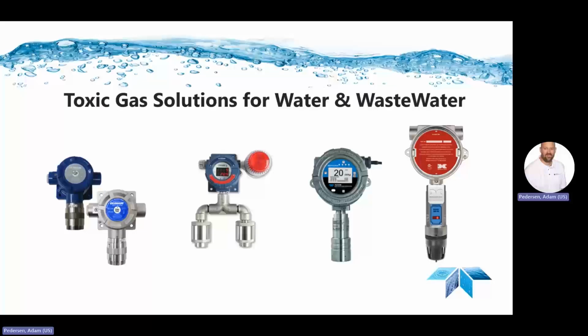I also want to highlight some variety we have for gas detection solutions for toxic gases. Our OLCT 100 is a blind gas detector that just received North American approvals. This is going to be all the way on the left. This is a great option for someone with many points of detection that's looking to cover them in an inexpensive manner. Our iTrans unit next to that has the ability to have dual sensors on one unit. The Meridian next to the iTrans can have up to 3 sensors on one transmitter. And then lastly, all the way to our right, the 700 series is a rugged transmitter. It's fully potted and sealed, eliminating failure from water ingress, corrosion, or damage from vibration. So these are all great solutions for toxic gases in your water and wastewater facilities as well.